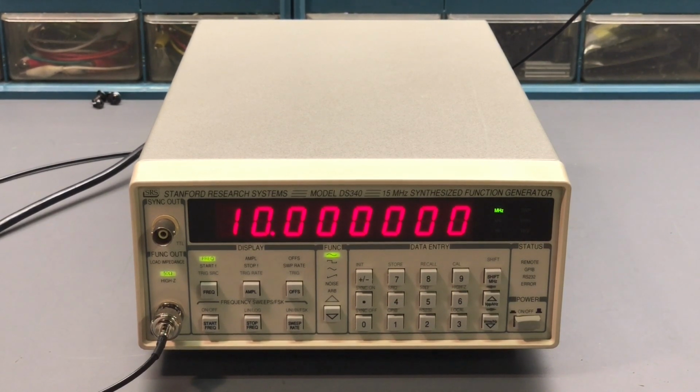So while I'm making the adjustment, I'll keep the camera focused on the frequency counter instead of the instrument, so that you can see the effect of the adjustment that I'm making. You can see really what the actual output frequency is. If I go between the two, the frequency counter and the DS340, it's just a lot of extra camera movement. So let me show you exactly how you move around in the settings for the cal bytes.